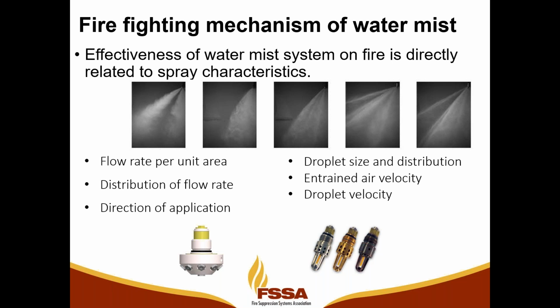Sometimes when you're dealing with higher ceilings and other types of areas where the fire might be further away from the spray head or the sprinkler head itself, the velocity that you project that droplet out of the spray head is really going to determine how effective it is in penetrating the fire source and the core of the fire at the floor level. Next slide.